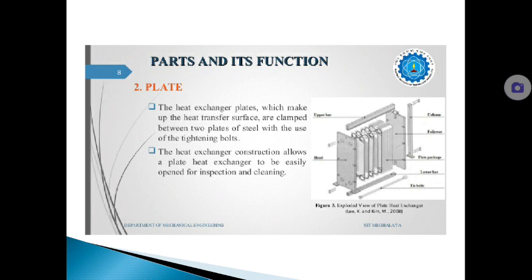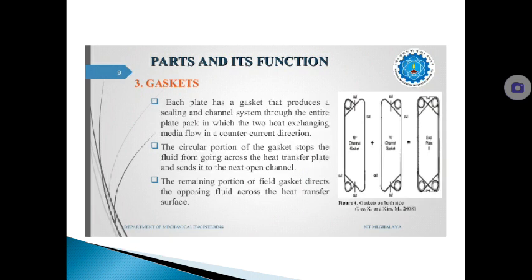Then the second part is the plates. These plates, or heat transfer surface, are clamped between two plates of steel with the use of the tightening bolts. Its construction allows a plate heat exchanger to be easily opened for inspection and cleaning purposes.